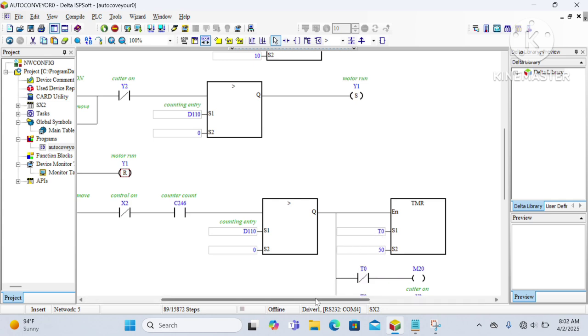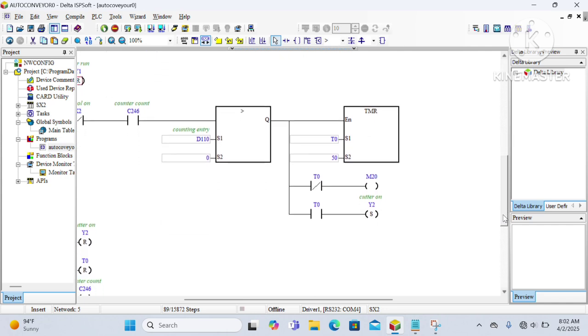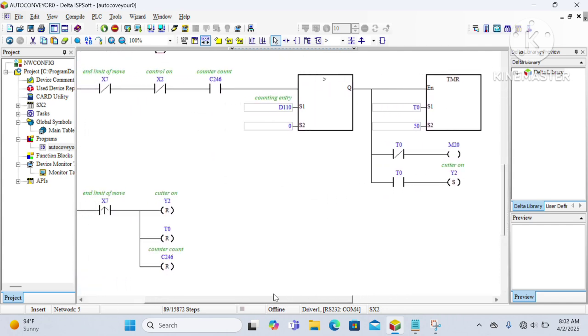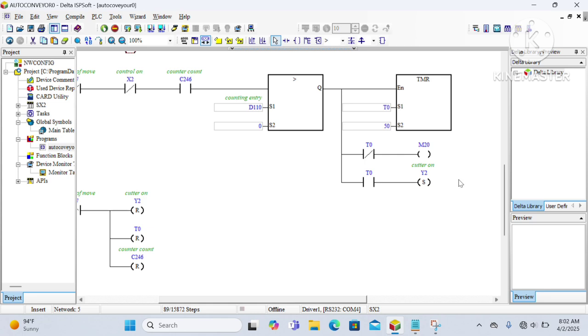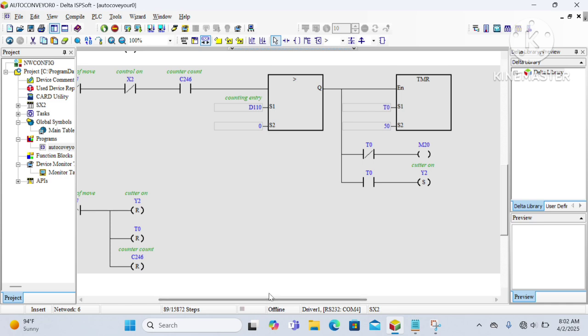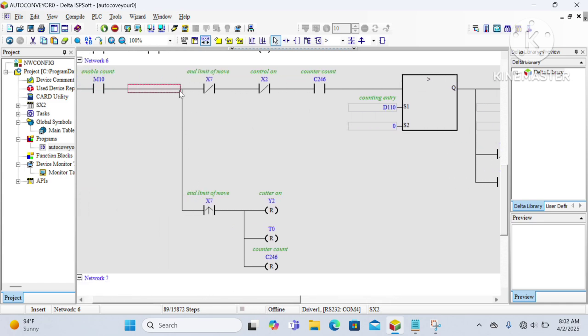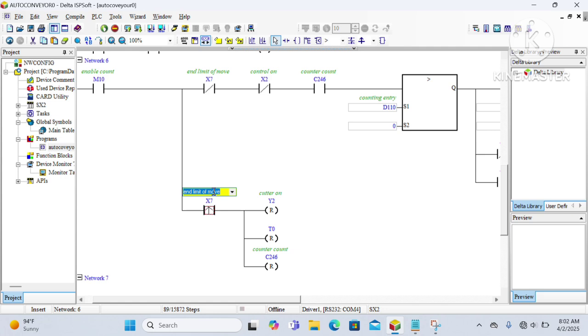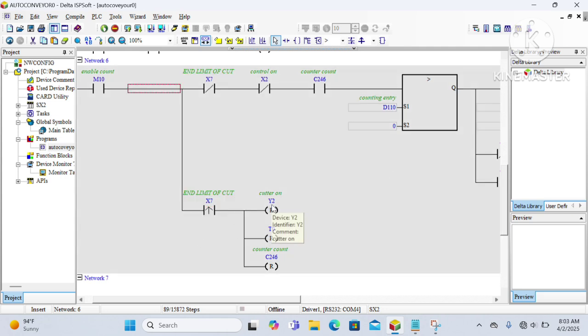To activate the cutting tool, we use a time delay with a timer. This timer prevents the cutter from enabling while the gear motor is still running. Finally, we reset all enabled outputs. The limit switch X7 resets all these outputs — when the limit switch is pressed after the cutter comes down and the pipe is completely cut, it activates and resets everything.